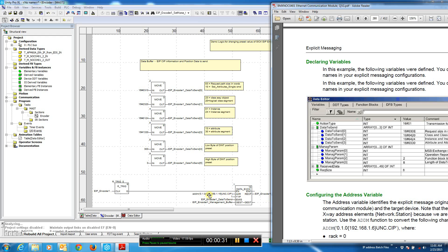In this command, we're going to set the IP address that we're going to send the actual explicit message to, and it's a very explicit string message that we have to send. The help can assist you with this, but in this case it's ADDM brackets, and then it's a string with single quotes: RAC module channel 010 in the case we have here, then the curly brackets, the IP address, end curly brackets. Then we have to do unconnected, UNC.CIP, and then a regular bracket at the end.